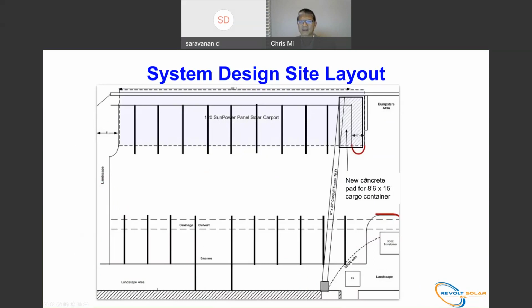Within this container, we're going to install 6 battery packs. Those batteries are rated at 62 kilowatt hour each, and they will be mounted on the concrete. We're going to run a conduit from the container to the building, to the electrical room.